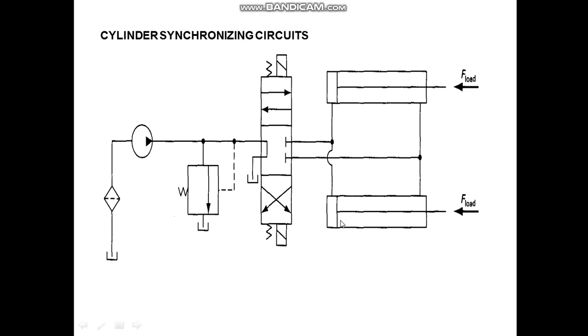You must keep this point in mind: if the load acting on both cylinders is the same, then the pressure created by both loads will be the same and extension will start at the same time. To achieve the same velocity for cylinder 1 and cylinder 2, the areas must be the same — the blank end (piston) area of cylinder 1 and cylinder 2 must be equal, and the rod end area must also be equal. Only when cylinder areas are equal and loads are equal will both cylinders extend and retract at the same time.